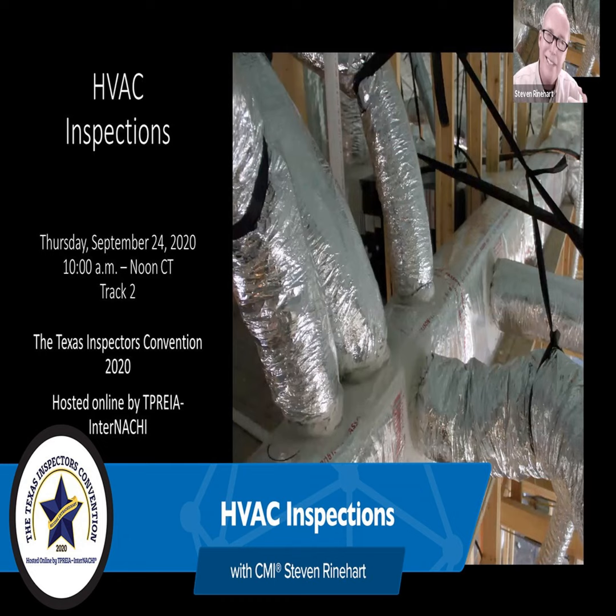But if I see a lot in there, or like in a water heater, if I see a lot of residue on that big round burner, it's coming from somewhere. That means that wall is getting thinner and thinner, and it could open up and leak into the breathing air that's being heated. That's going to be a problem. So I'm looking for a good clean burn.